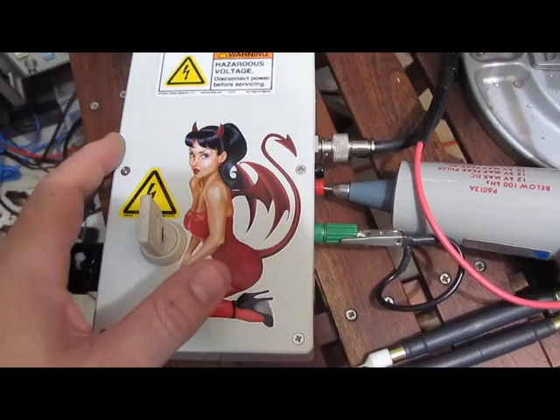I have a bunch of Teflon shims inside of the box now to protect the new capacitor bank and isolate it from other high voltage areas. It seems to work fine. It's not breaking down at all. It should be okay to run these few tests. We're running high enough voltages now.